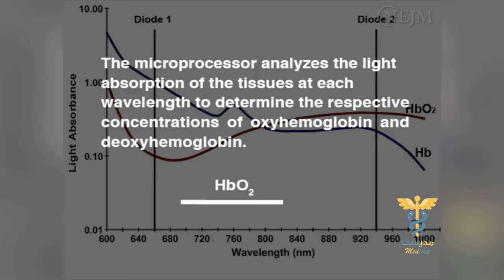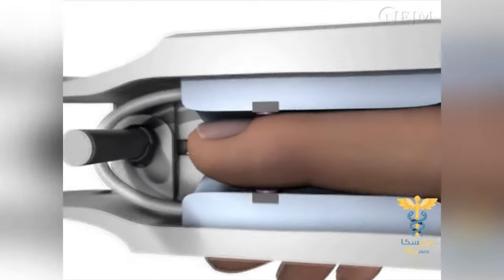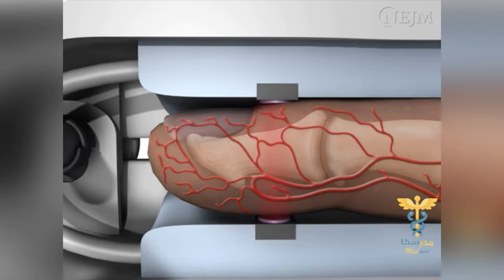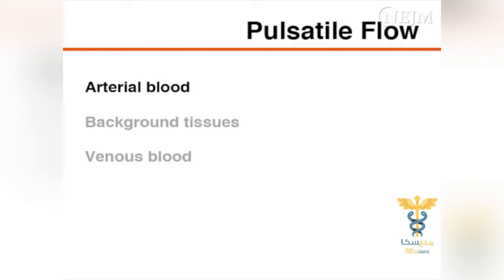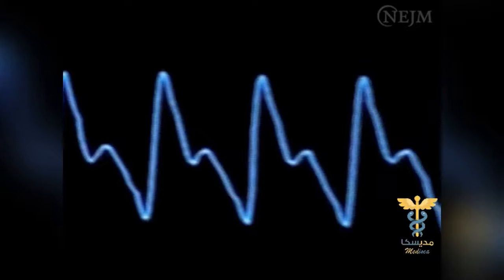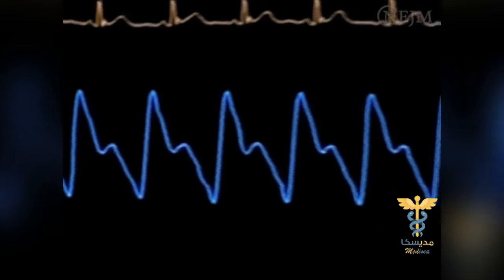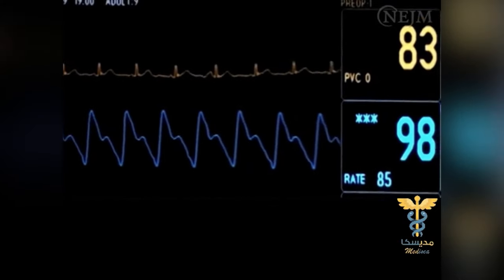The microprocessor divides the concentration of oxyhemoglobin by the sum of the concentration of oxy- and deoxyhemoglobin to determine the arterial blood oxygen saturation, SpO2. The probe is positioned so that the photodetector and light-emitting diodes face each other, with layers of tissue between them. The photodiodes turn on and off several hundred times per second to record the light absorption during pulsatile and non-pulsatile flow. During pulsatile flow, the light absorption of arterial blood, background tissues, and venous blood is detected. During non-pulsatile flow, only the light absorption of background tissues and venous blood is detected. The microprocessing unit compares the light absorption during pulsatile and non-pulsatile flow to isolate the light absorption of arterial blood and thus determine the arterial blood oxygen saturation.